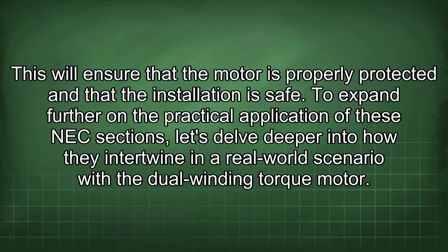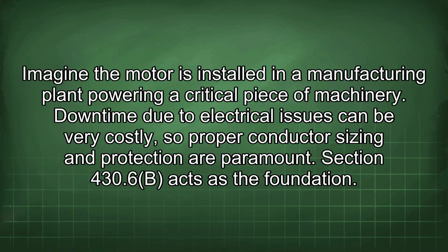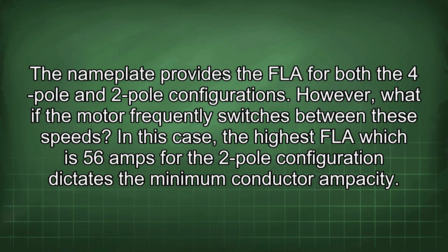To expand further on the practical application of these NEC sections, let's delve deeper into how they intertwine in a real-world scenario with the dual-winding torque motor. Imagine a motor is installed in a manufacturing plant powering a critical piece of machinery. Downtime due to electrical issues can be very costly, so proper conductor sizing and protection are paramount. Section 430.6b acts as the foundation. The nameplate provides the FLA for both the 4-pole and 2-pole configurations. However, what if the motor frequently switches between these speeds? In this case, the highest FLA, which is 56 amps for the 2-pole configuration, dictates the minimum conductor ampacity.